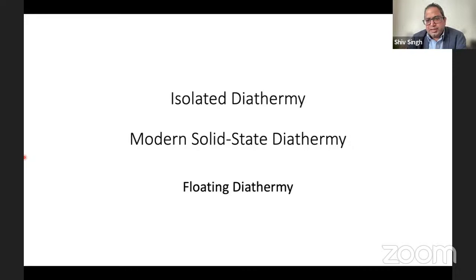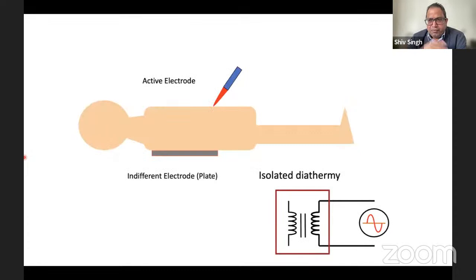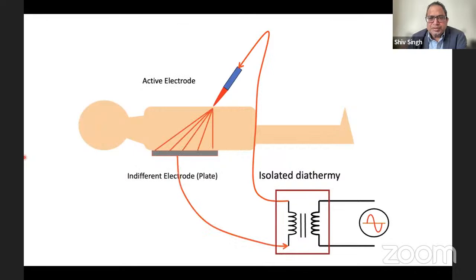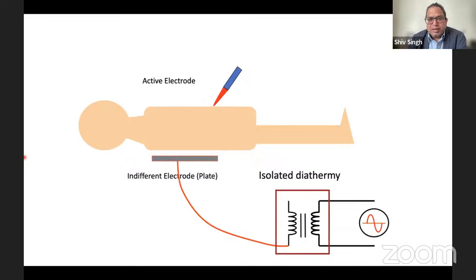Just like I explained for the isolation power system, the same thing is used here. You have a primary circuit and then a secondary circuit, and this is no longer live or neutral. This is just line one and line two, and that's completed through this circuit. If there is a disconnection, it won't work at all, the circuit won't be completed. But again, if this was a single plate and you had not got a complete contact, you could still get diathermy burns. So we moved on to the next step.